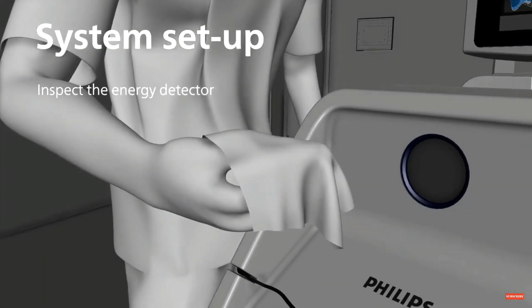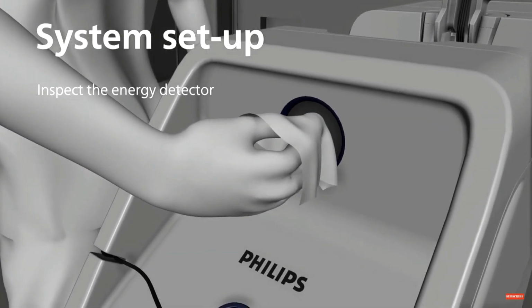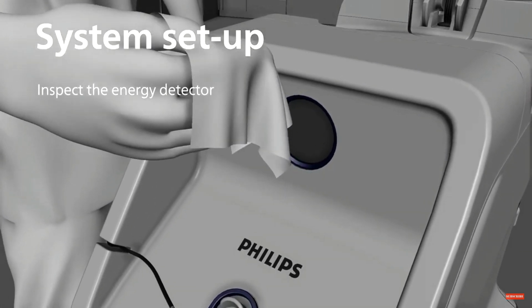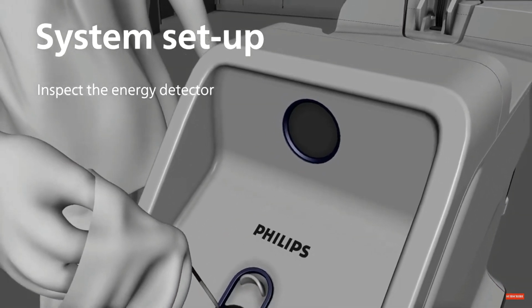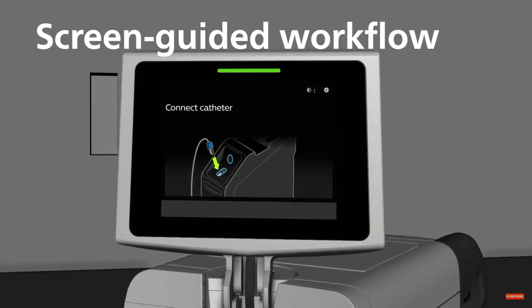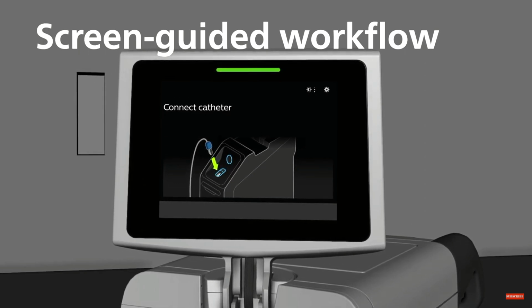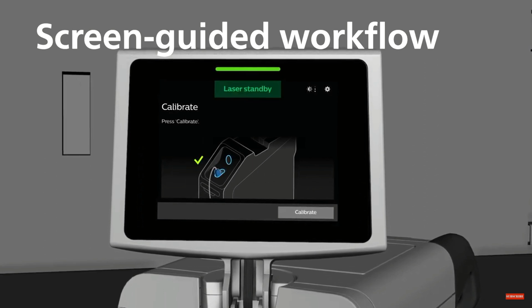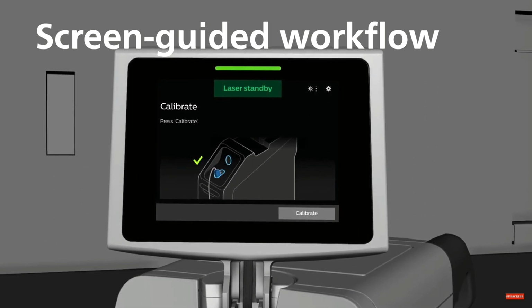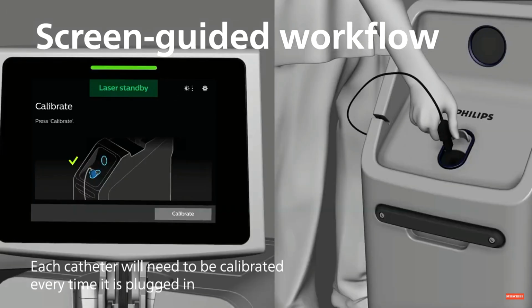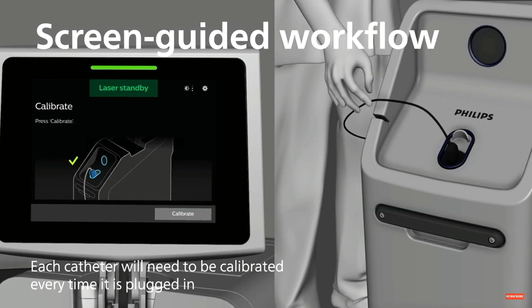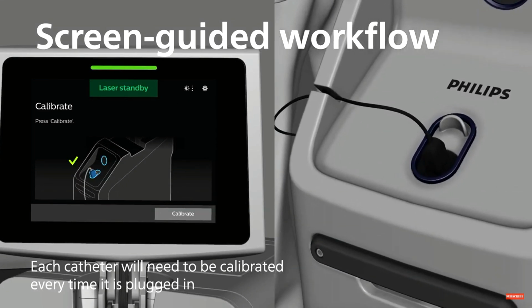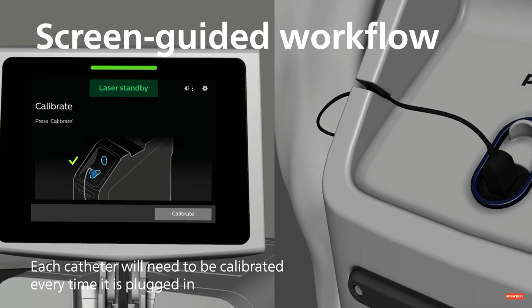Inspect the energy detector. If it is dirty, clean the surface of the energy detector with an alcohol prep before and after each use. When initialization completes, the system will present the Connect Catheter screen prompt. It will take less than 30 seconds for this screen to appear after the system is powered on. Insert the desired catheter for the procedure. Use the provided catheter retaining feature to hold the catheter away from the detector during calibration. This will provide more clearance from the sterile area.